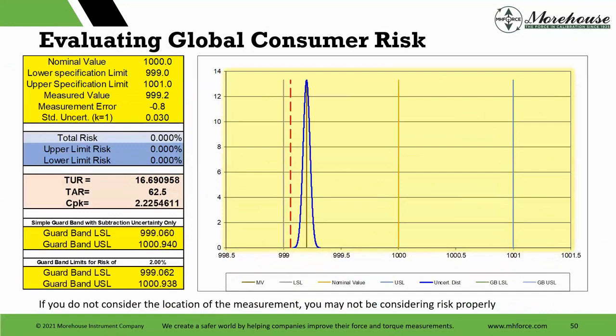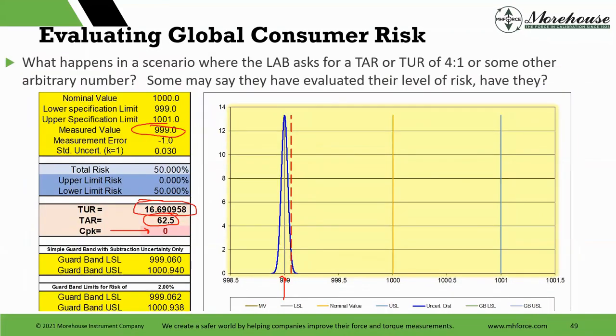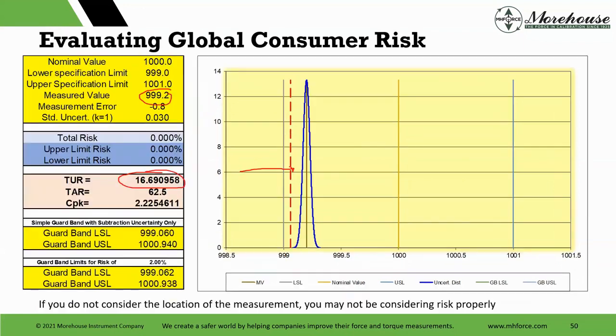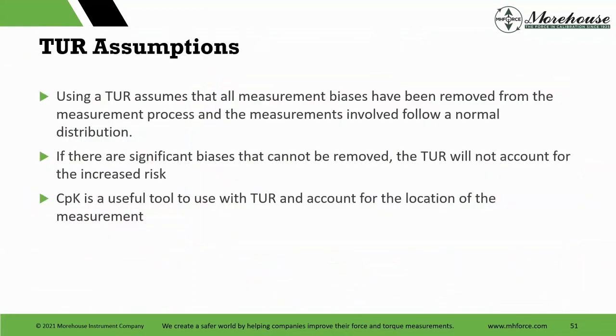This is not taking measurement uncertainty into account, right? That's what it is. So if you do not consider the location of the measurement, you may not be considering risk properly. And here, with that TUR of 16.69, we just moved the measured value over to bump it back in specification to show. So if you look at those here, it's on the line, it's bad. If we slide it over just one count, it would be in. Adjust, not adjust. Just really important to analyze this, and CPK is a good tool to do that.